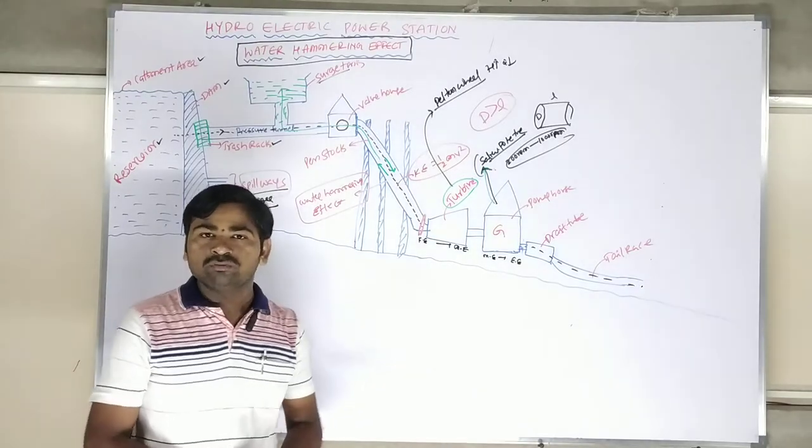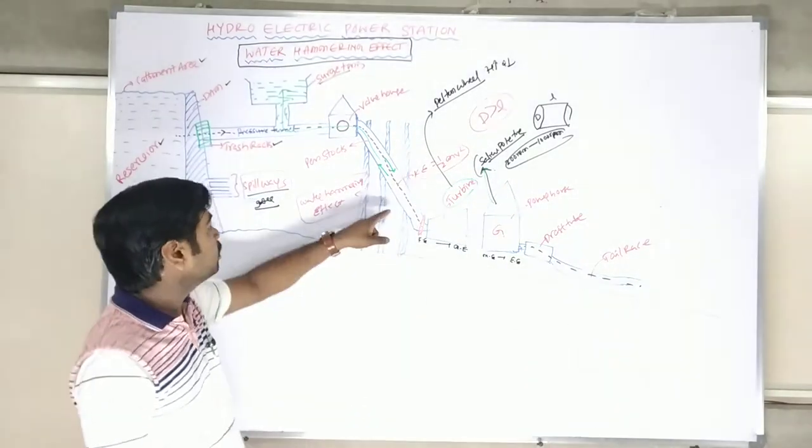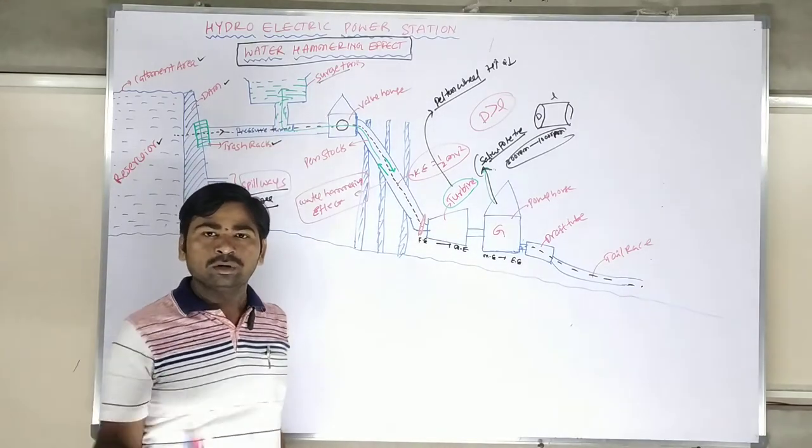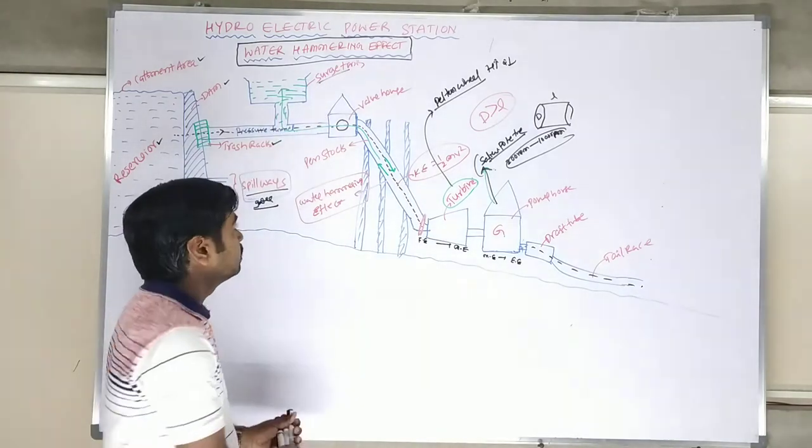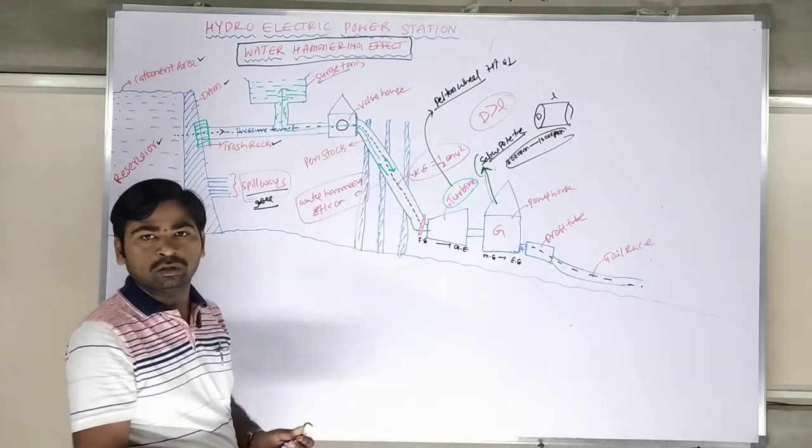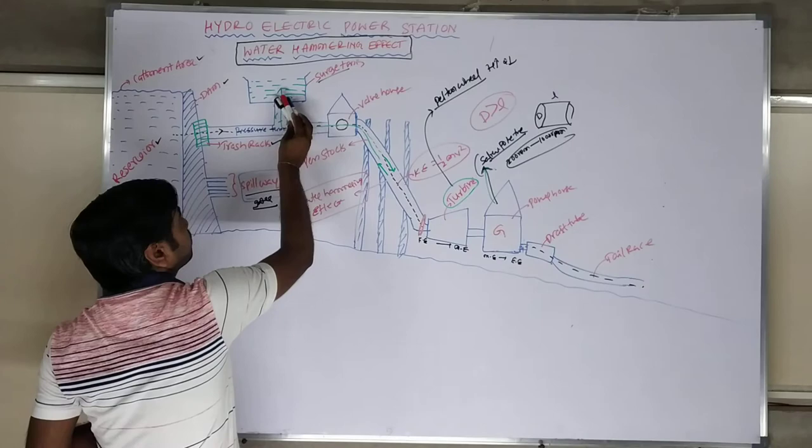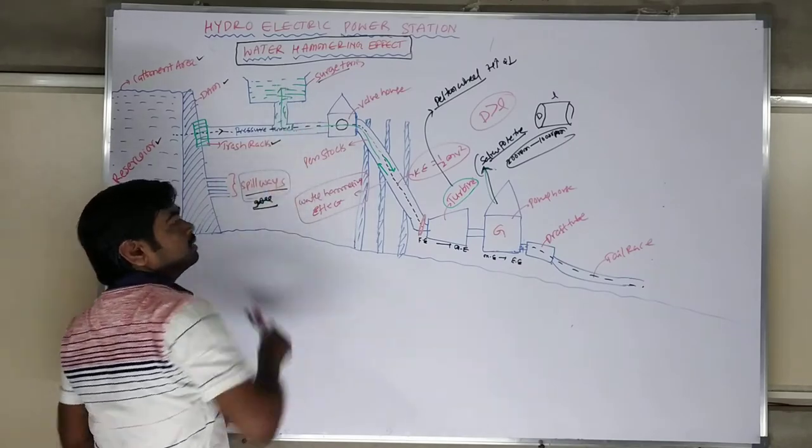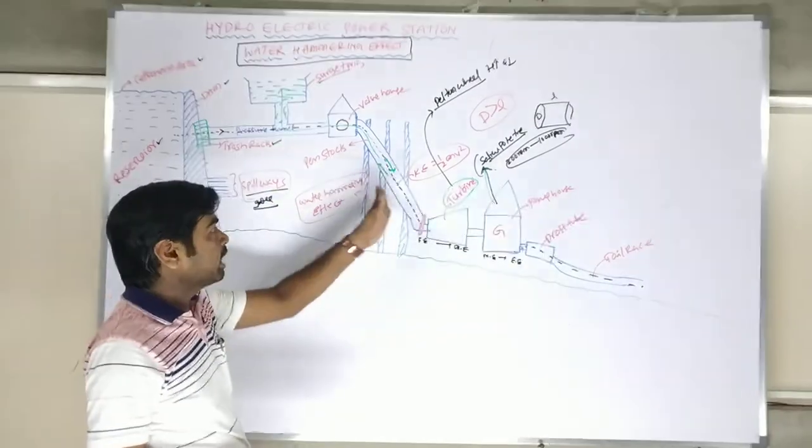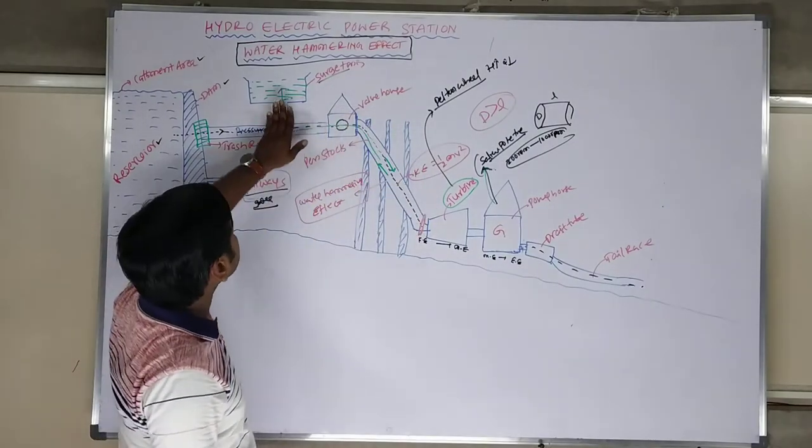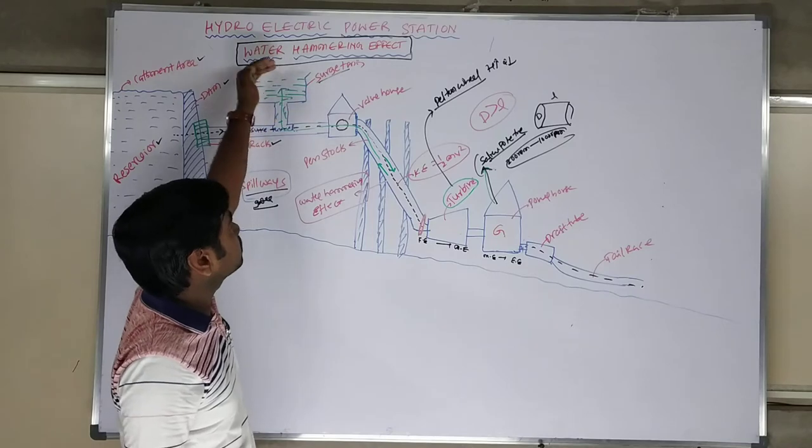To reduce this water hammer effect, we have to use a separate equipment called a surge tank. What the surge tank will do is handle the high pressure or low pressure of water, which will be sent back to the surge tank. Water will keep on increasing in the surge tank. When there is high pressure, that extra high pressure water will again go back and bypass into the surge tank.